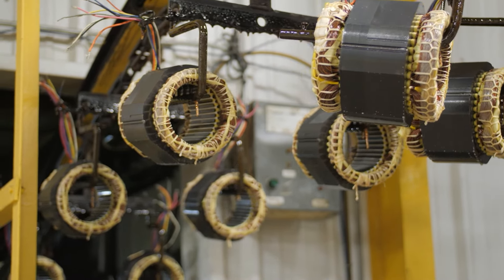Features that can be included while remaining fully compliant include ambient temperature above 40 degrees Celsius, auxiliary terminal box, special frequencies with the use of an inverter, special grease, and several others. However, the standard also has a list of features that may be included but do not fully comply with IEEE 841, though they do allow the motor nameplate to read 'IEEE 841 features.' Some of those features include noise levels higher than specified, NEMA designs A or C, and larger than standard frame sizes, among others.